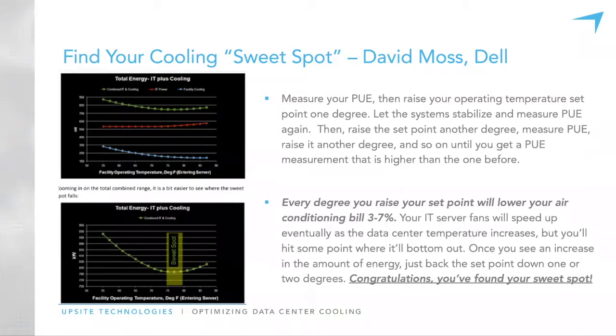You measure your PUE, then start raising your set points one degree at a time. To be honest, I'm impatient, and I've found it takes about 2 degrees to affect compressor cycle change. But one degree is good - you raise the set point and allow the system to stabilize. I do a lot of this: walking up and down the rows the CRAC unit is supplying air to.